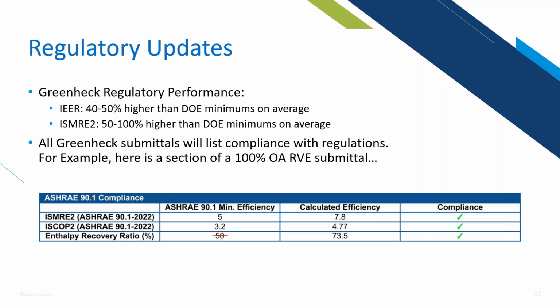And regardless of what it is, if you've seen a Greenheck submittal before, you'll notice that we provide a compliance sheet with it. So right here, you can see that the ISMRE2 is well above what the ASHRAE 90.1 minimum efficiency says by 2.8. And then they actually give you that enthalpy recovery ratio, and they'll compare it to the IECC, or I guess in this case the 90.1 requirement. But as we know by stretch code, that 50% isn't right. It's actually 70%. But the good thing is with Greenheck, and we'll get into this in a little bit, we're well above the 70% as well.